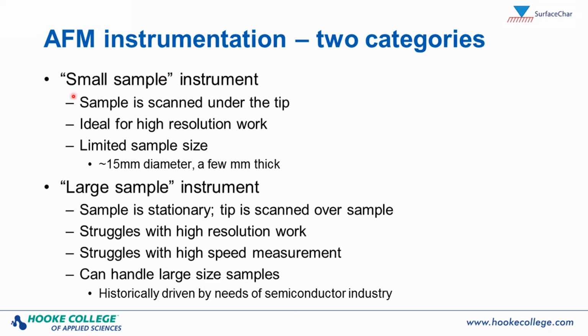There are what we refer to as small sample instruments, where the sample is what is moved and scanned under the tip. This is really the kind of instrument you want for high resolution work, like atomic scale work. The problem is that it comes with a very limited sample size. If the sample is being moved under the tip, and imagine these samples are being moved tiny amounts, 15, 20 nanometers, you can't have a large mass being moved around. So the sample size is typically limited to about 15 millimeters in diameter and only a few millimeters thick.